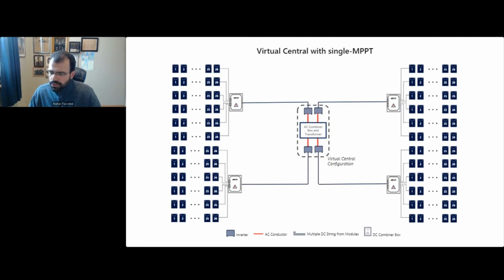And so let's look at the next one. The other solution in the market has string inverters with a single DC input. In this case, the string inverter has a single DC input, which allows the use of DC combiner boxes or wire harnesses with aluminum feeders to reduce DC cabling costs. However, since these inverters have only one MPPT, the energy harvest is lower when compared to the multi-MPPT inverter solution. Okay? So while electrical balance of system costs can be reduced, energy production is also lower. Okay?